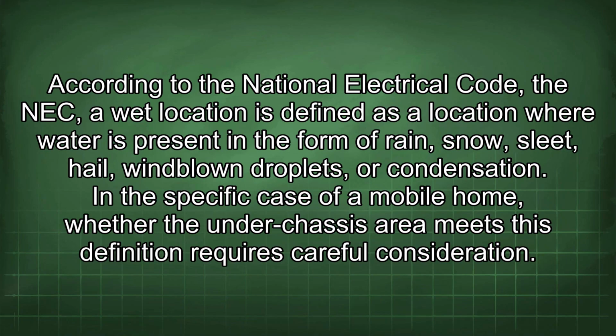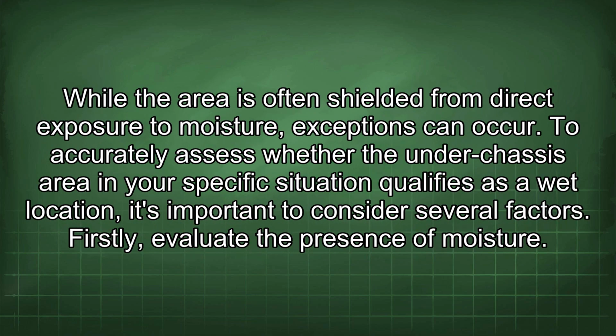According to the National Electrical Code, the NEC, a wet location is defined as a location where water is present in the form of rain, snow, sleet, hail, wind-blown droplets, or condensation. In this specific case of a mobile home, whether the under-chassis area meets this definition requires careful consideration. While the area is often shielded from direct exposure to moisture, exceptions can occur.